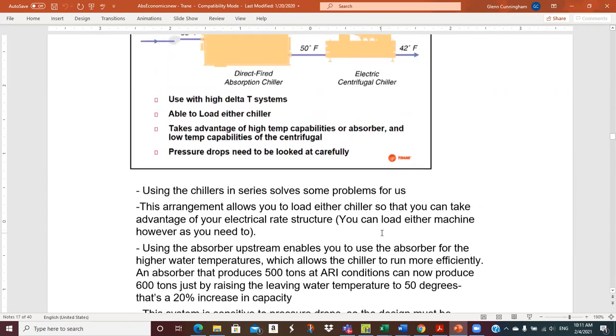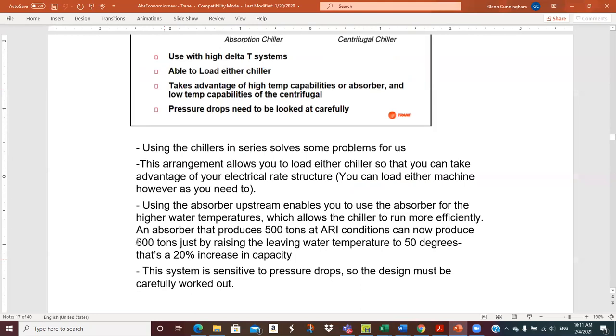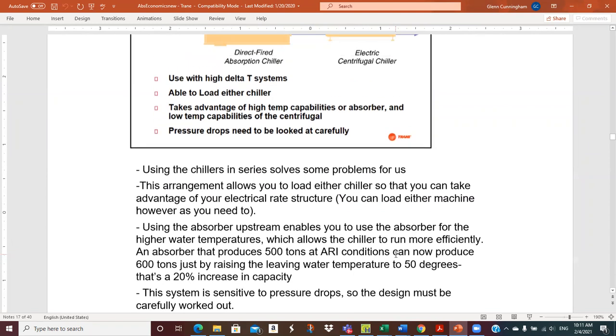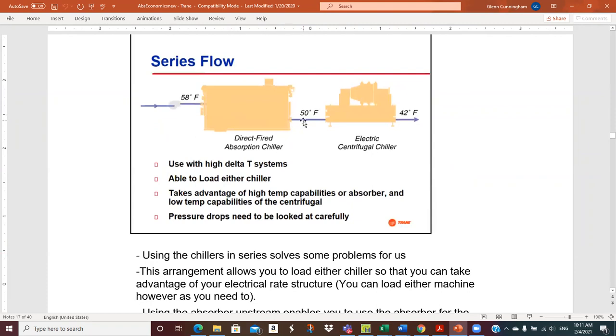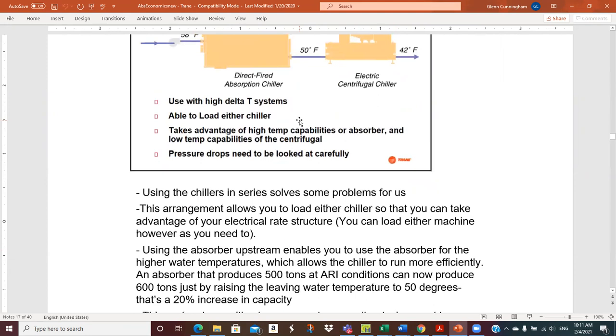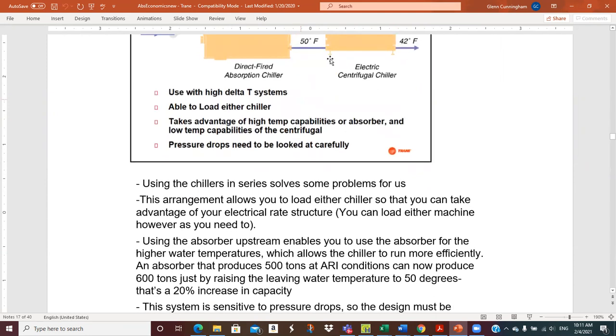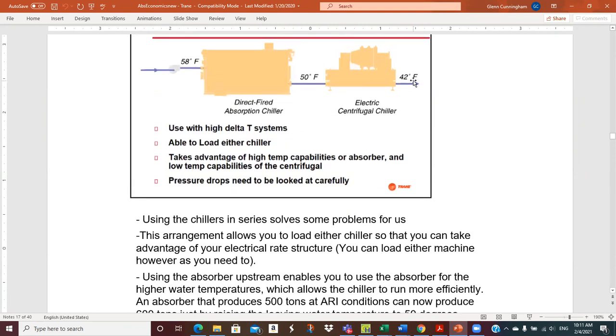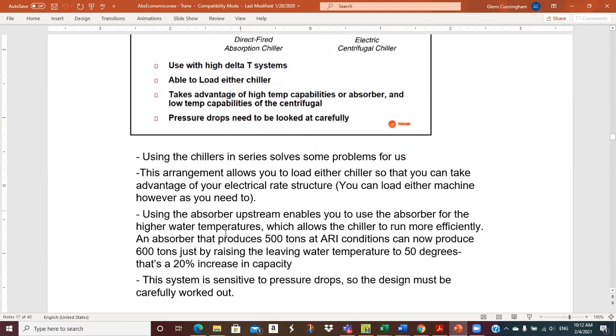Conditions, and now by raising, well, it says raising the leaving water temperature, but we're putting in warmer water to it. So I guess he's really talking in terms of leaving water temperature. This thing at 50, which means we went in at 58, we have a 600-ton chiller, which could be interesting. Now, in the dead of summer, you're still going to need 42-degree water, but in the spring, the fall, and even the winter, when you have a large building that still needs air conditioning, it may be able to get by with 50-degree water just fine, because it's really dehumidification that's the issue on having the cold water. So it's an interesting concept.